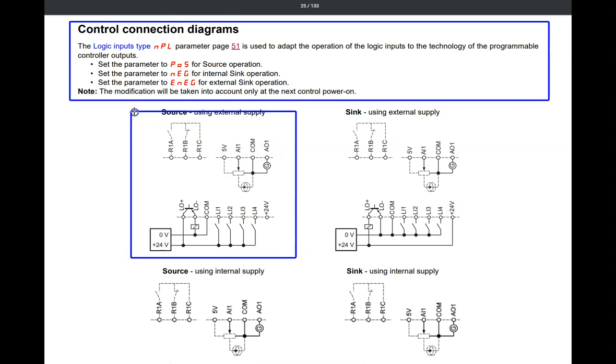So under source operation, using an external source. An external source would come from another control system like a programmable controller. You take a zero volt from that external programmable controller. You connect it to your common on your drive. And this 24 connects to the switches. When the switch is closed, you have plus 24 volts at those digital logic inputs. And you have a run command or a true condition in that case.